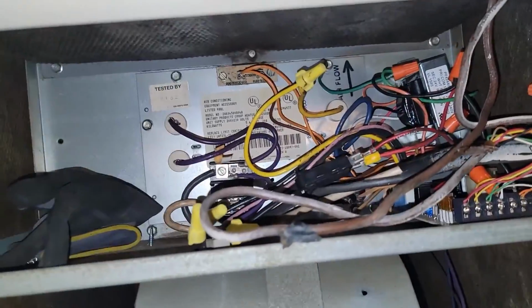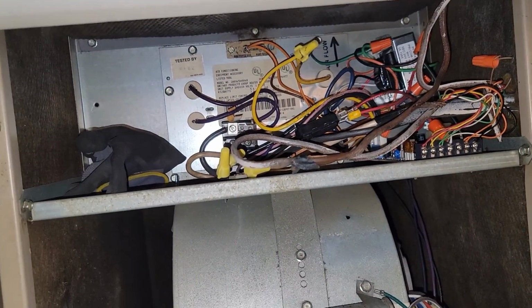Oh, and it's on. So it looks like the problem's in the condenser. All right. So the fuse did not blow whenever I took the thermostat wires loose from the outdoor unit. So I isolated the outdoor unit, turned the power back on to the air handler inside, that 230 volt air handler, because this is a heat pump unit, heat pump split system. And now the fuse doesn't blow. So I know for sure it's in the outdoor unit, but where could it be?